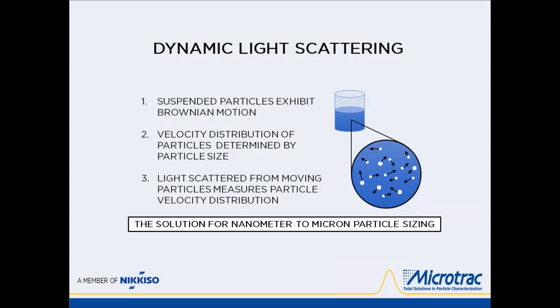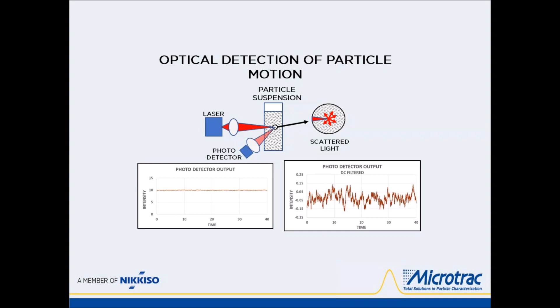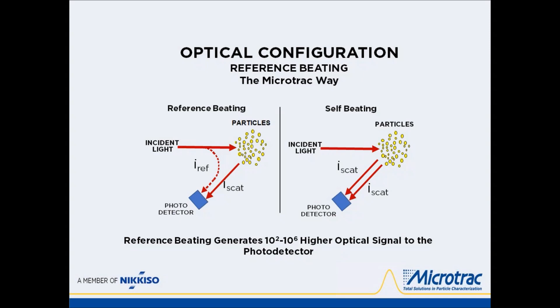Here's the basic principle when it comes to dynamic light scattering. The laser goes in, interacts with the particles, and that shifted light, that interacted light that comes back is measured by the photodetector and then transformed into the output. There's two different ways that you can compare the reference light to the shifted light from the particles. One is a reference beating method, where a portion of the reference light is used specifically as a comparison. The other one is a self-beating method, where you're trying to gather all of the light, the reflected light as well as the shifted light from those particles. Using the reference beating method, you can get much, much higher signal to noise ratio than you can with the self-beating method.